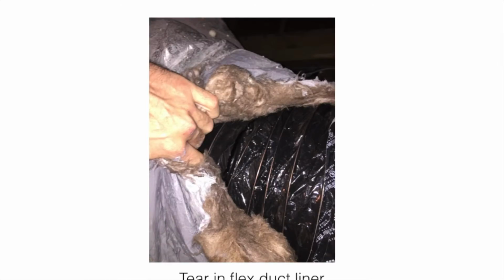This is a picture of a tear in a piece of flex duct that I found, and there was no tear in the outer liner, only a tear in the inner liner, and the way I found it was feeling the airflow that was flowing through the insulation that's in my hand. I then peeled back the insulation and found this large hole. When flex duct tears, it has a tendency to tear larger and larger, which is really bad for duct leakage.